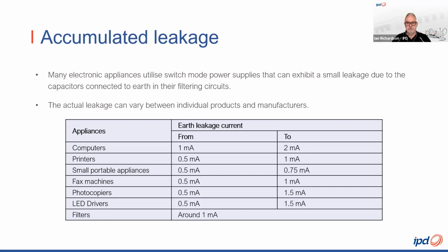it becomes clear that there could be an accumulated leakage problem. If you consider a typical office environment, you've got 10 computers on a final subcircuit. Perhaps that's not unusual. This is potentially a 20 milliamp leakage, because we know that computers, because of their switch mode power supplies, could have a leakage between 1 and 2 milliamps. So taking the upper limit, 10 computers, 2 milliamps, we're now at 20 milliamps. We're into that threshold where a normal 30 milliamp RCBO can trip.